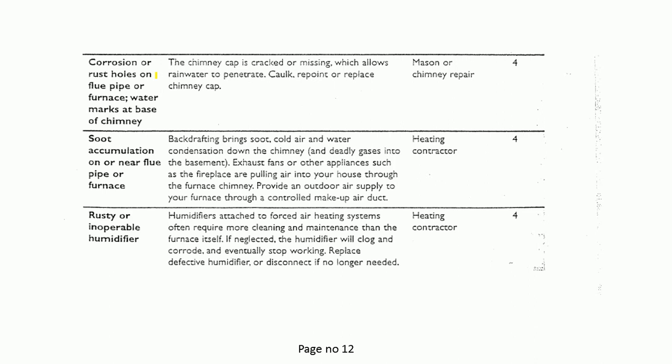Another three cases: corrosion or rust holes on flue pipe, furnace, water marks of chimneys. This one, the chimney cap is cracked or missing, which allows rainwater to penetrate. Caulk, repoint. I need a mason or chimney repair for soot accumulation on or near flue pipe or furnace. This is the reason. Again, I'm going to read it again. For a rusty or inoperable humidifier, all that detail, heating contractors for.